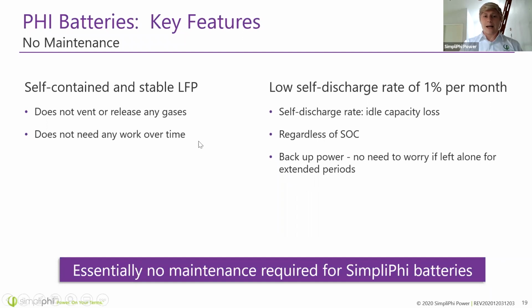Our batteries do not need maintenance. They are self-contained and stable, so they don't release any gases and don't need ventilation. There's really no maintenance needed at all, unlike a lead acid battery where you'd have to do watering, topping off, and even specific gravity checks. A lot of times you have to sit there during the equalization charge and check the specific gravity. It's just a big pain.